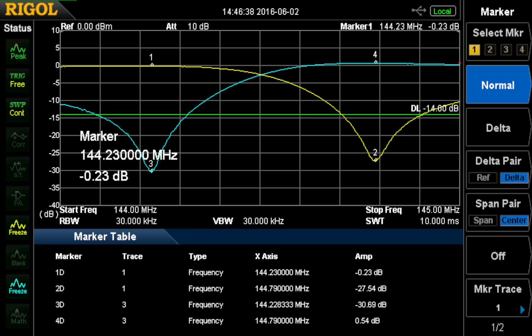Marker two is the null, notch, or reject frequency, at 27.54 dB down. Then it comes back up a little and stays around 10 dB, maybe 7 dB, at frequencies above that frequency. This is the kind of response you should see, and you can save that on the spectrum analyzer for later comparison to the return loss, which is the blue line you see, and I'll show you how we set up for that.